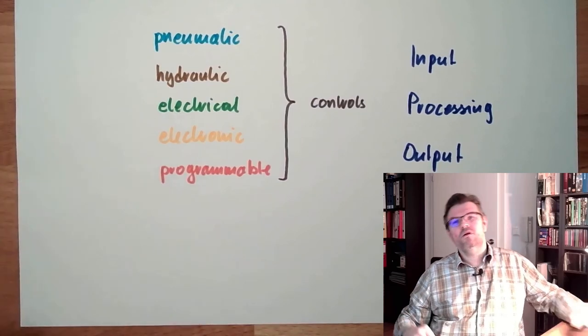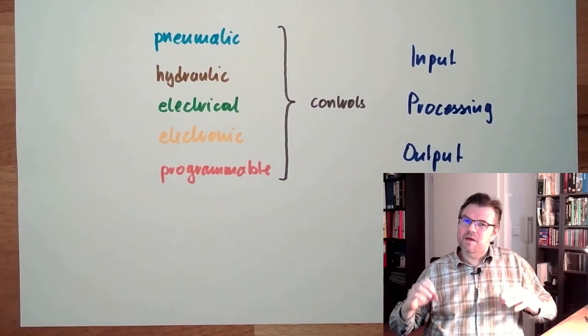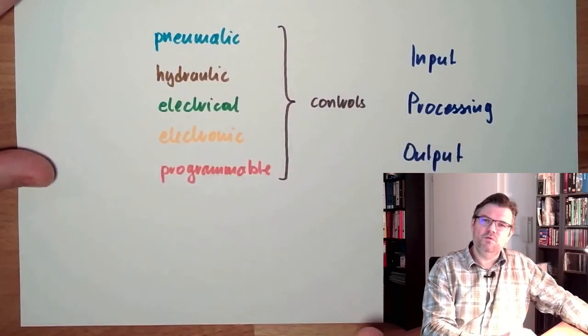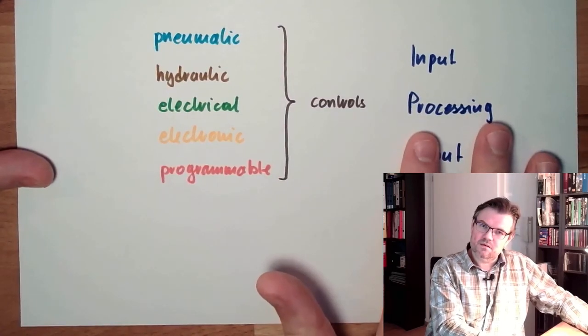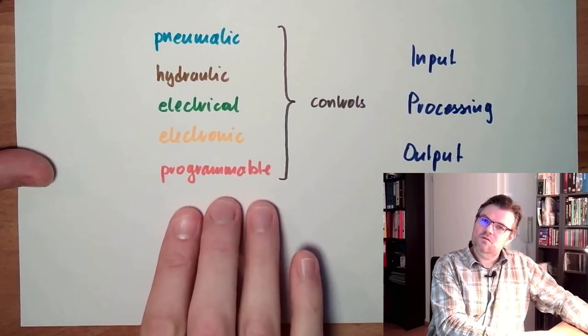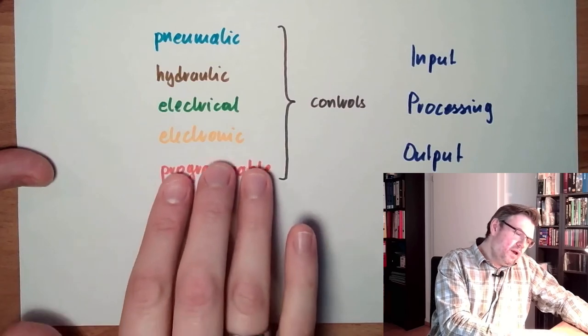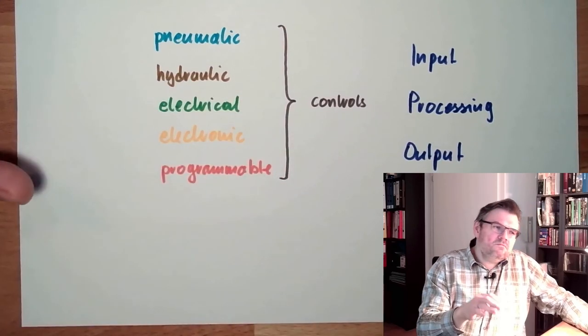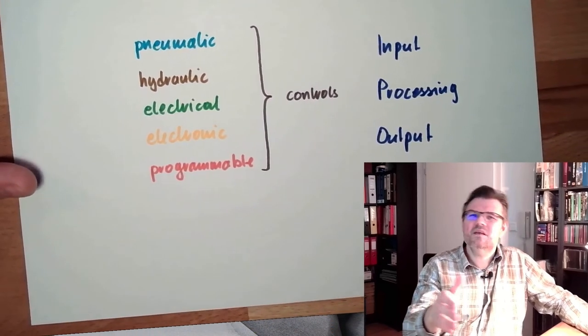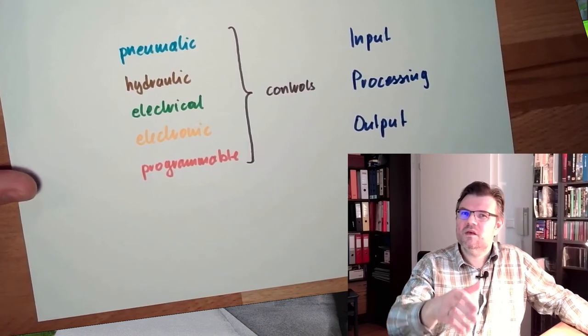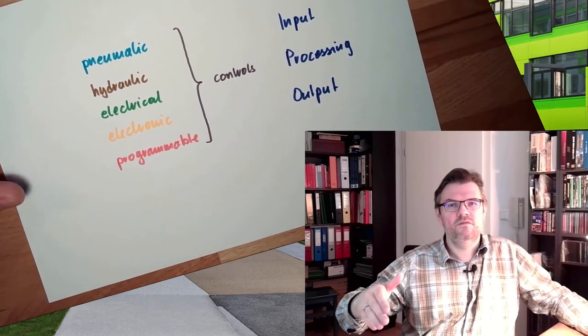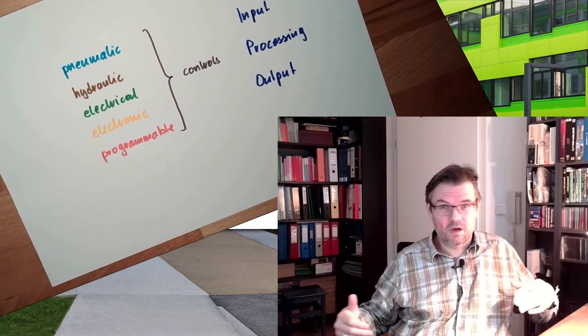Usually in a modern control system we have several elements, and we distribute even the processing. So if some programmable logic controller PLC is failing, we switch back to a lower level and at least can, maybe not that good but at least can do something, not let the unit or the machine get out of control.